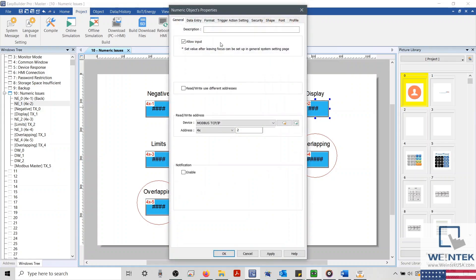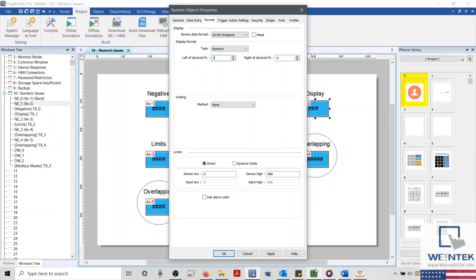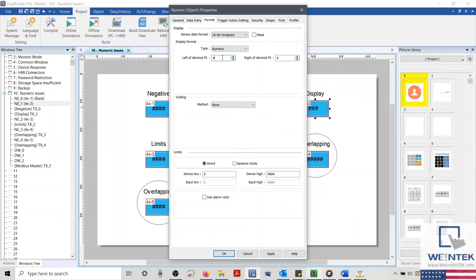As configured, this object can display a maximum of three digits. However, the address that it's set to read is currently holding a value of 3,000. So we'll need to update the character count within our display format to four. And checking my mock parameter guide, we'll find that this address should be able to display a maximum of 9,999. Meaning that with four characters and the correct limits, our Numeric Object should now accurately display data from our device.